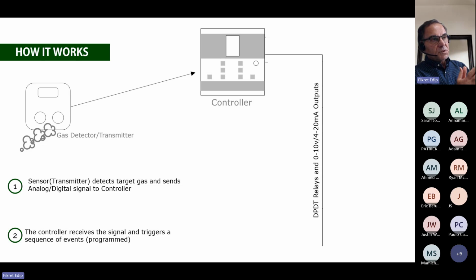4 milliamp means 0 ppm of that target gas. If it is receiving 20 and anything in between, now the controller will take an action. Similarly, the signal being transferred can be a digital signal, meaning that there is a protocol being used between the transmitter and the controller. And that digital signal, we typically call it a protocol.